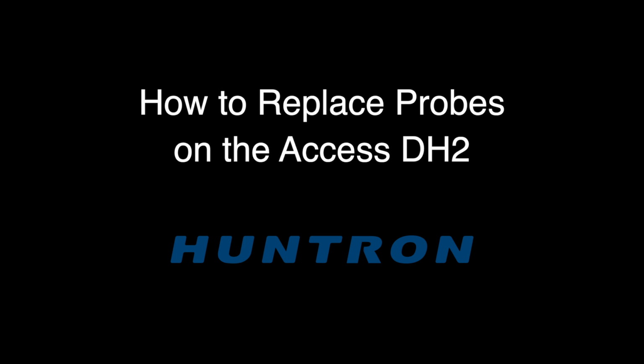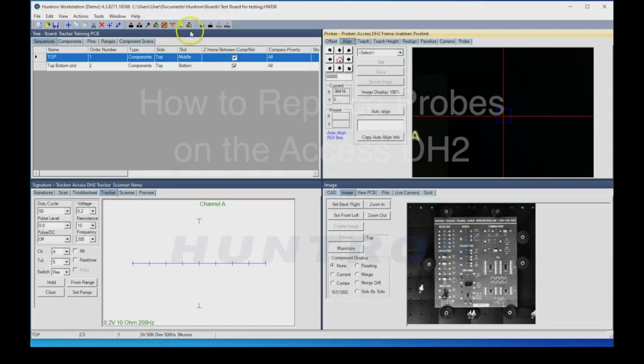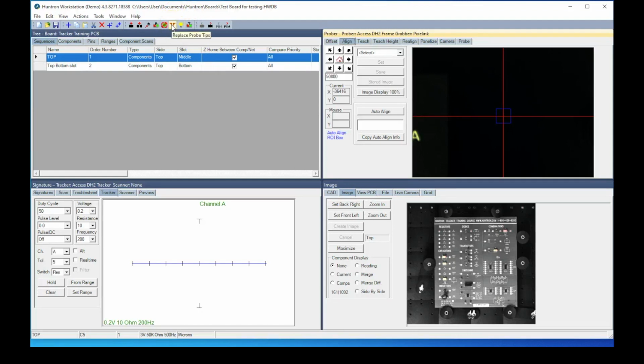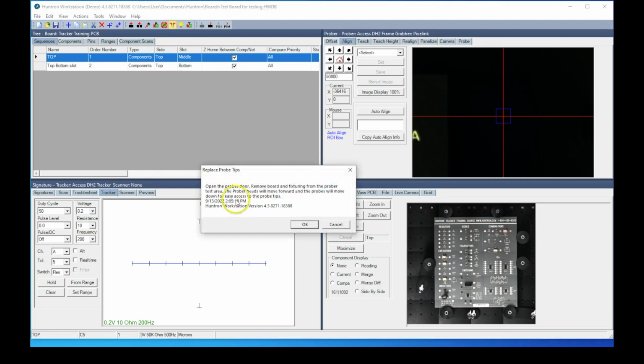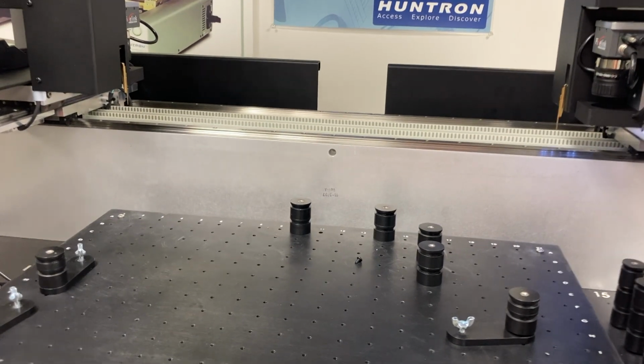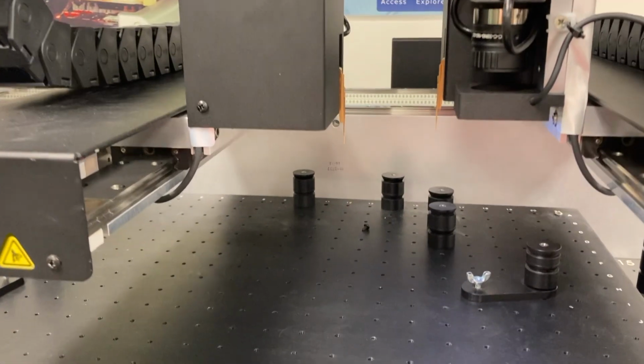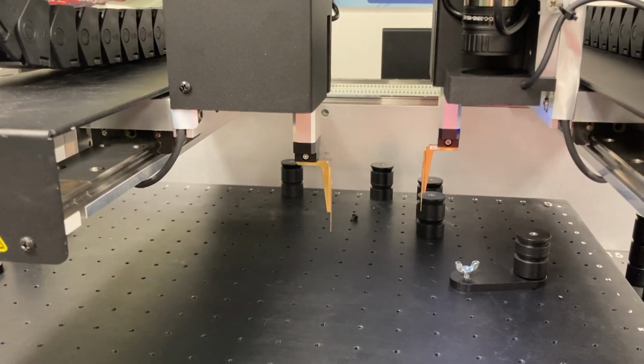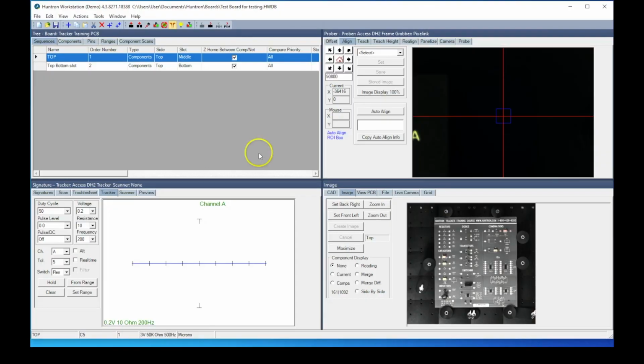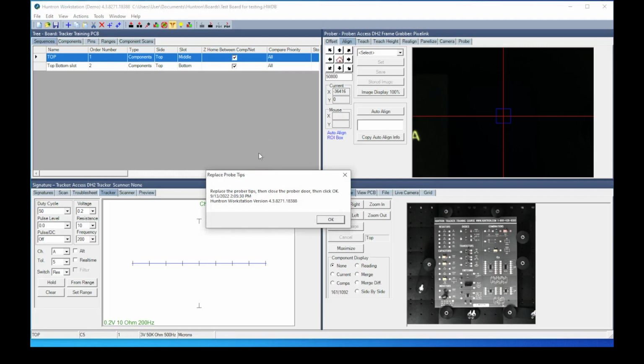In this video, we're going to cover how to replace the probe tips in an Access DH2 prober. We'll start by using the Replace Probe Tips button in the toolbar. When you click this button, you'll get a message to let you know that you need to remove any boards or plates that might be sitting in the prober that may obstruct the probes when they come down. The probe heads will come forward, and then the probes will lower down. This gives you access to the screws that you need. At this point, you can now go ahead and replace the probe tips as needed.